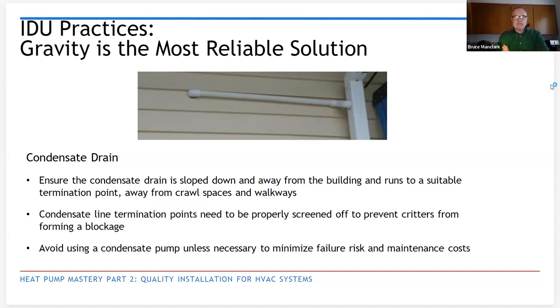Matt, I've got a question. Somebody is inquiring about, you're putting that into a drain spout. Are you worried about the condensate freezing at all in that drain? Nope. How come? With heat pumps, we're only going to have condensate in the summertime. On the indoor heads, we're only going to have condensate in the summertime. Wintertime, that condensate is going to be at the outdoor unit.